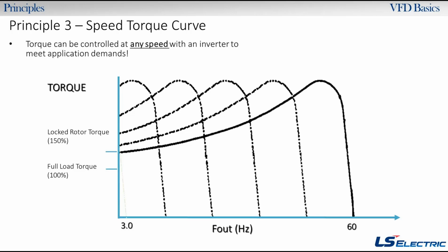And then we also have the speed reduction. It's great for fans and pumps and variable torque loads, or even just general industrial processes. Maybe you don't need to run your conveyor at full speed, or you don't want to run a speed reduction gearbox on it. Instead, you could just have a drive with a speed pot on it, for a few bucks, and you could reduce the speed with that.